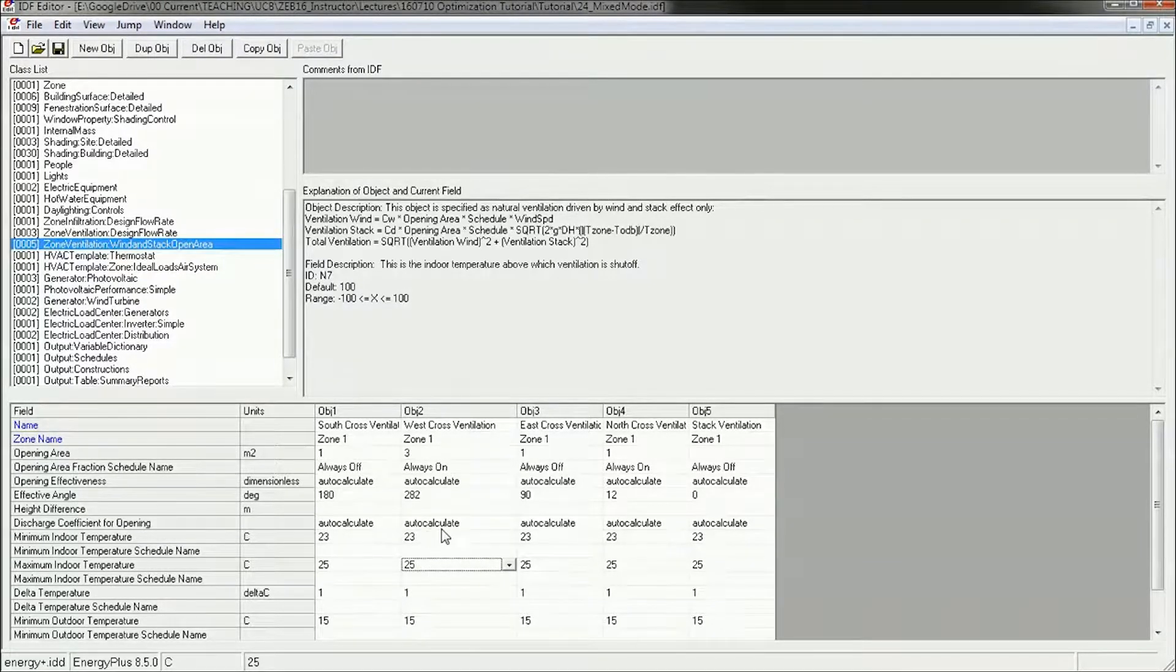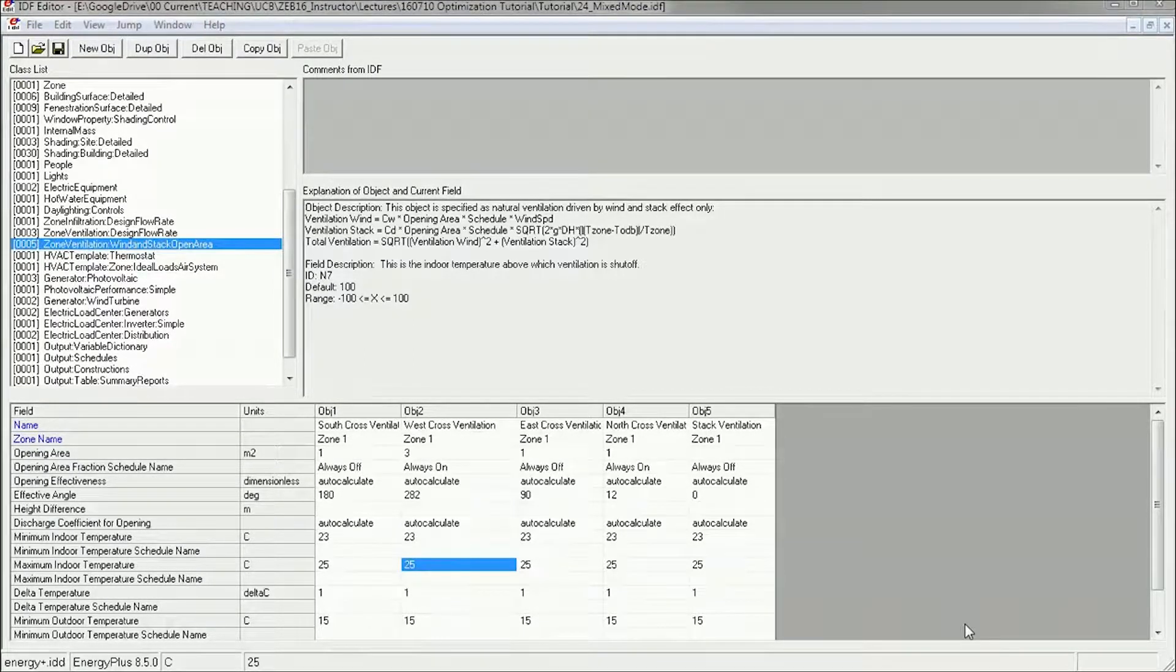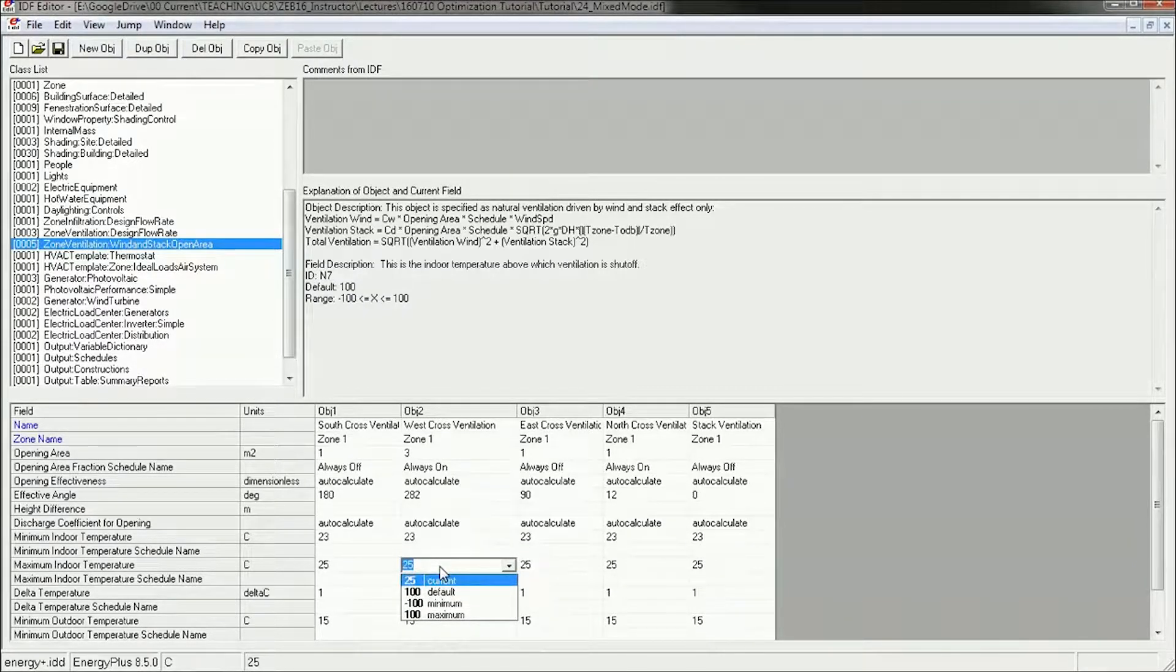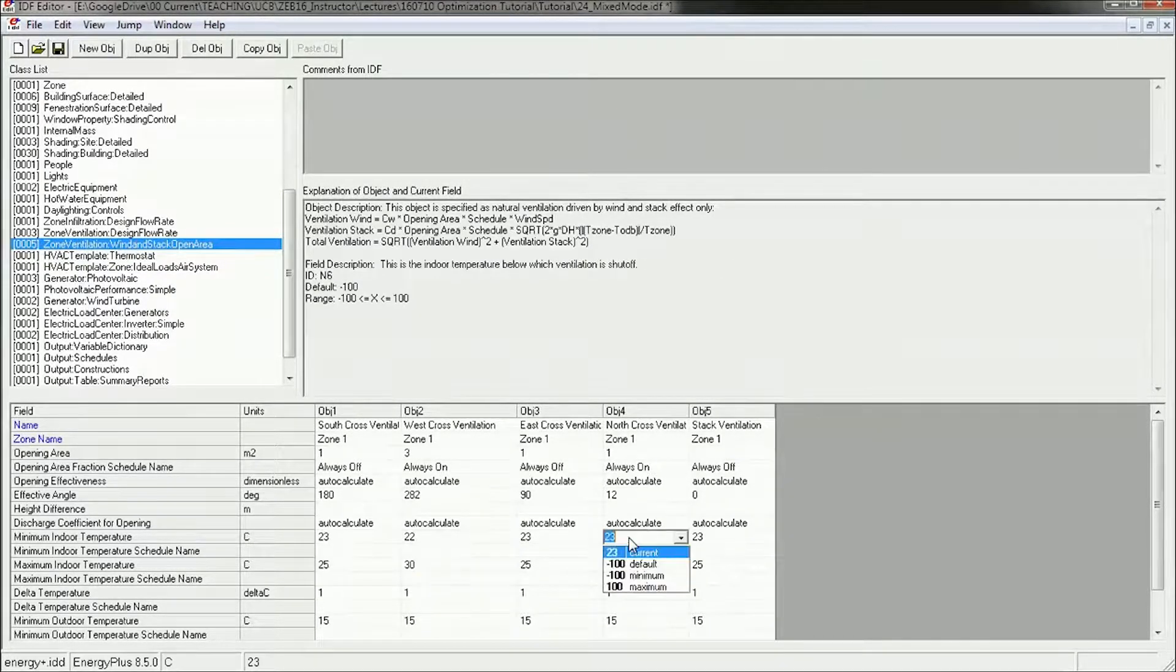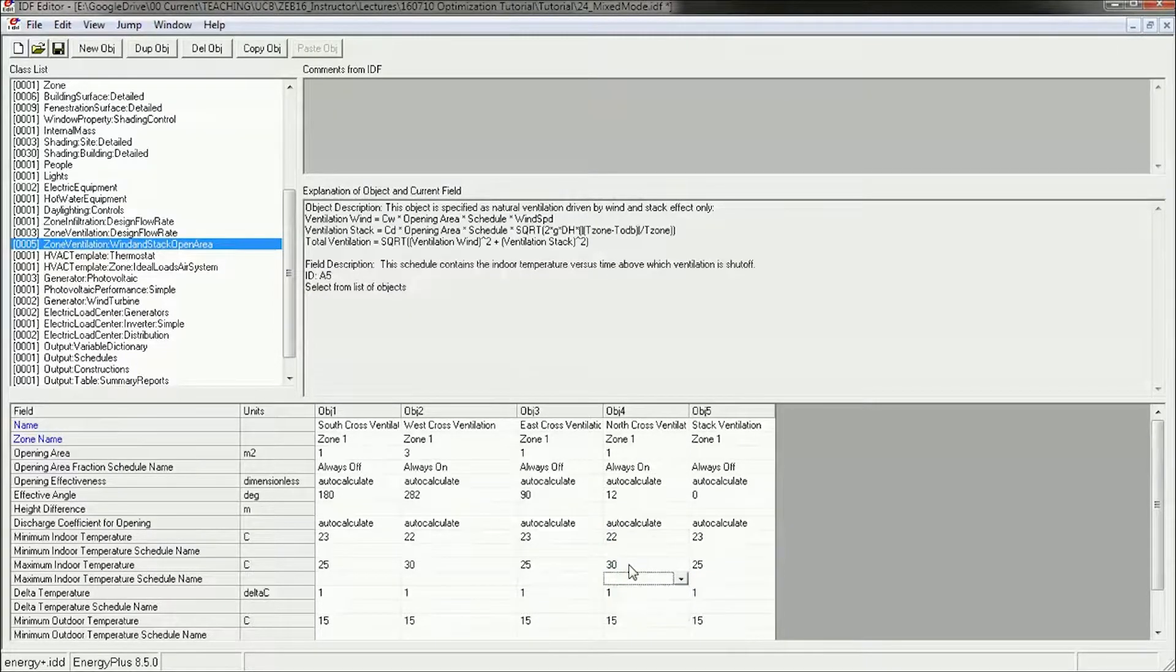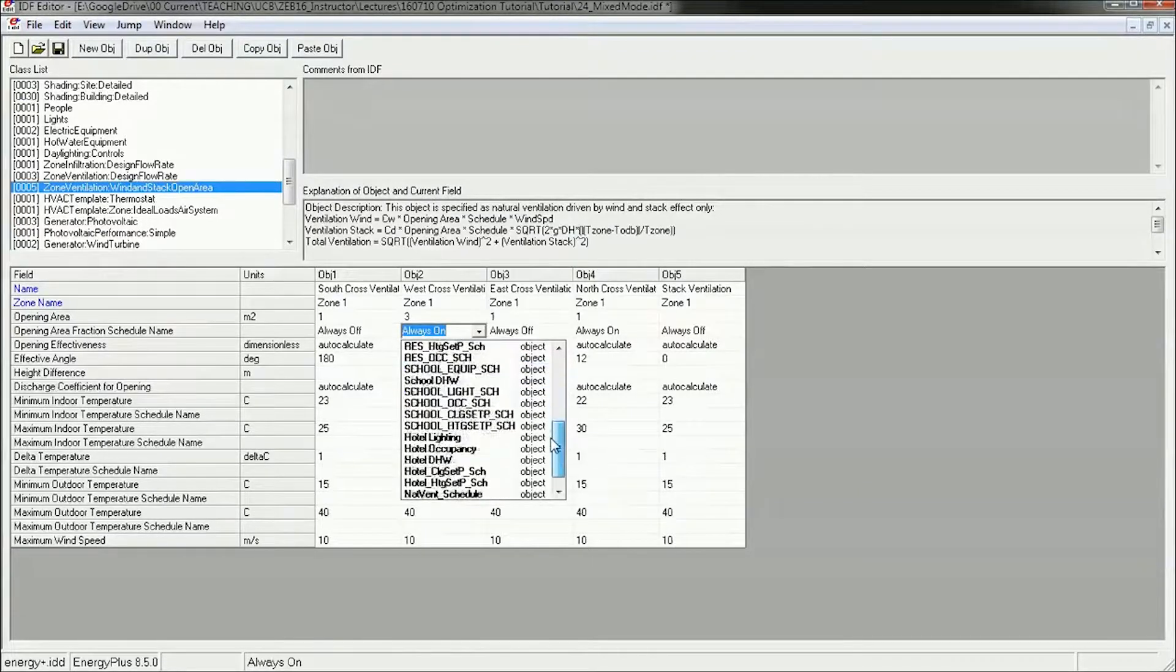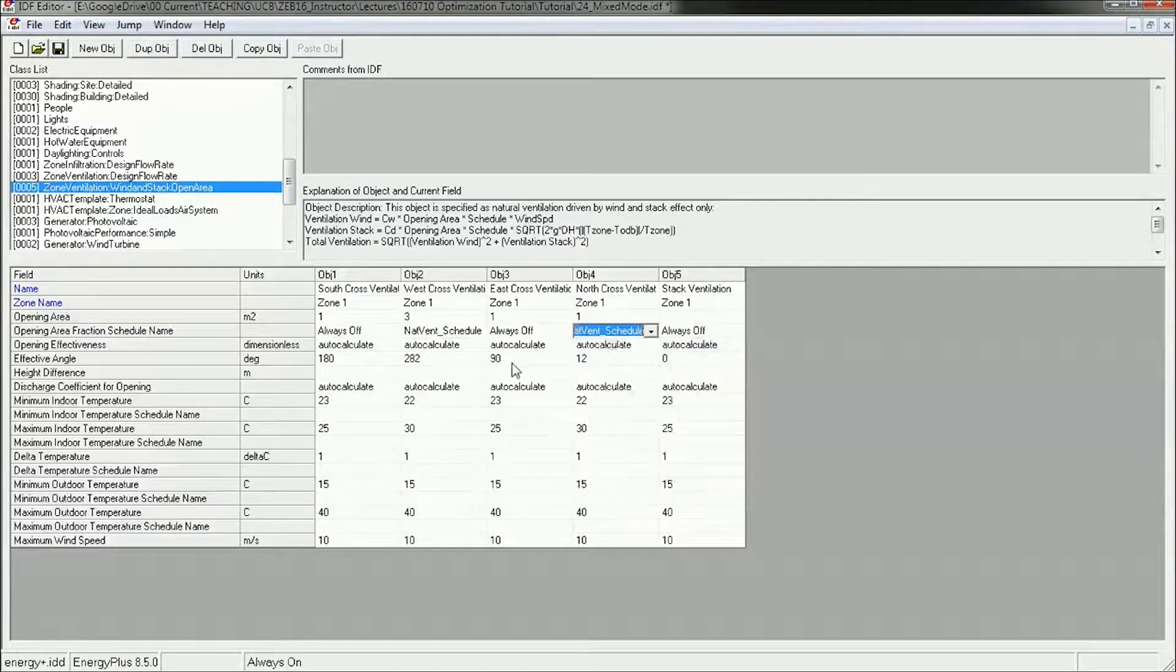And I did this primarily so that I wouldn't have the heating coming on when my windows were open. Now that I'm going to customize the schedules, though, I can expand this range. I'm going to have this be 30 degree high and a 22 degree low. I'm going to do the same for this one, 22 and 30. And then I need to change this from always on to the natural ventilation schedule. And I'm going to do that for this window as well, natural ventilation schedule.